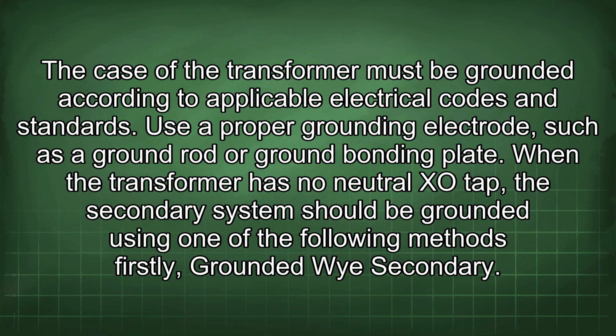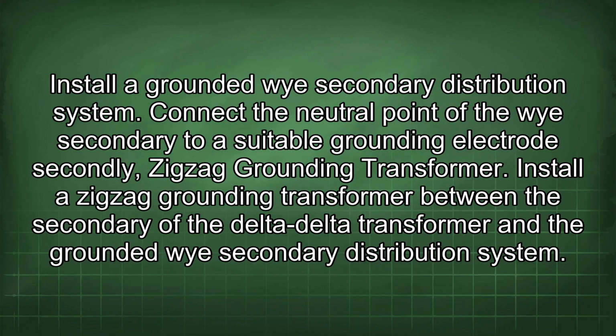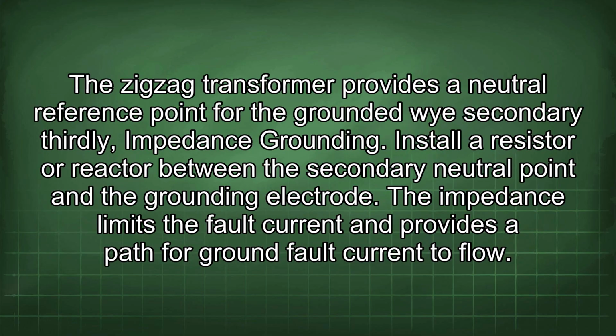Firstly, grounded wye secondary. Install a grounded wye secondary distribution system. Connect the neutral point of the wye secondary to a suitable grounding electrode. Secondly, zigzag grounding transformer. Install a zigzag grounding transformer between the secondary of the delta-delta transformer and the grounded wye secondary distribution system. The zigzag transformer provides a neutral reference point for the grounded wye secondary.